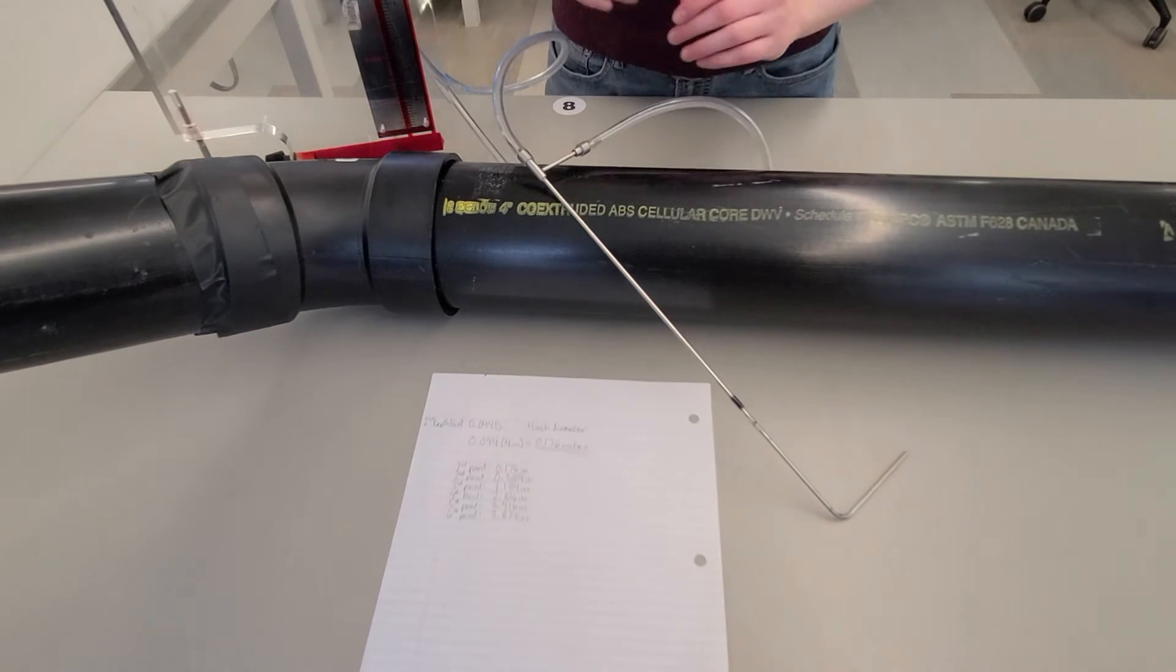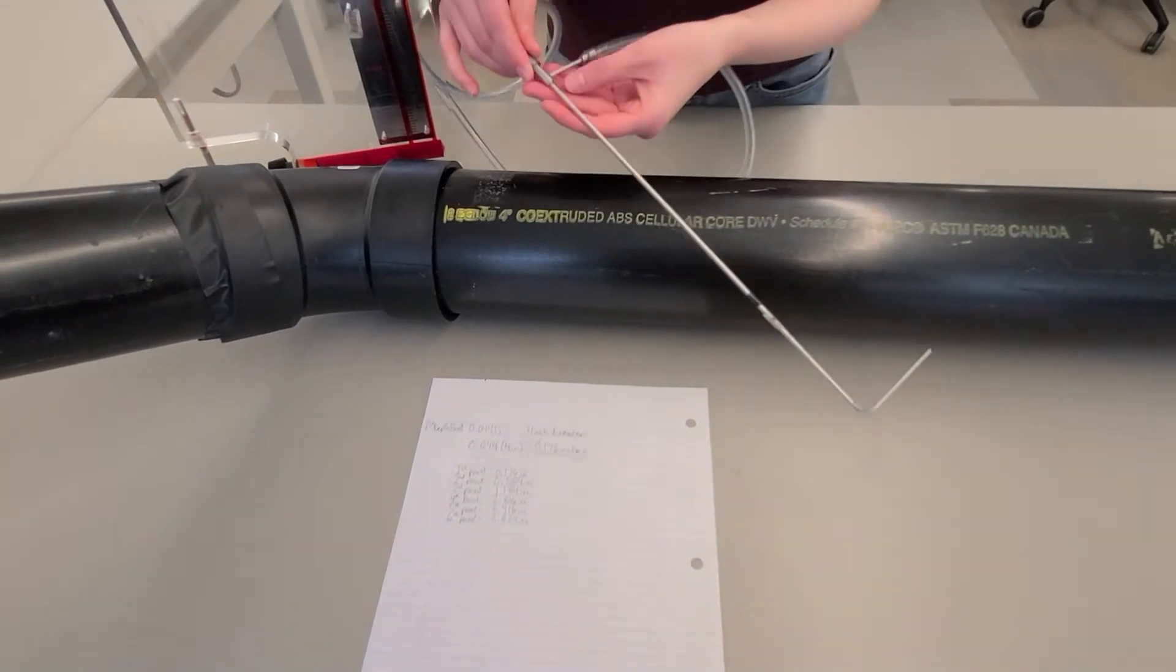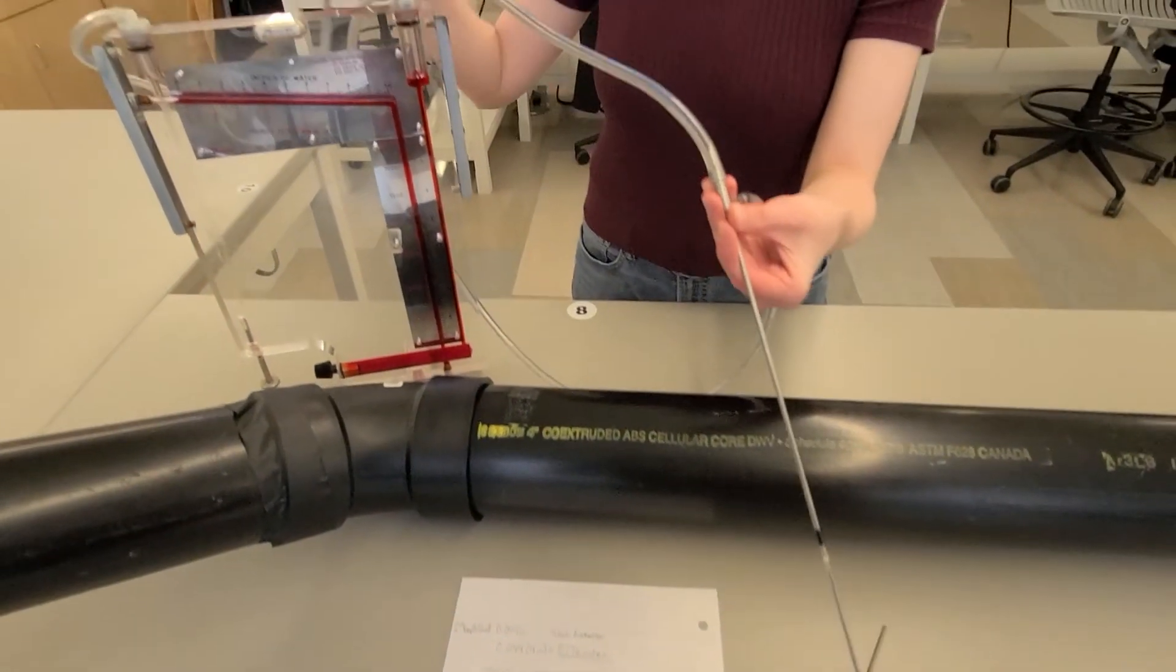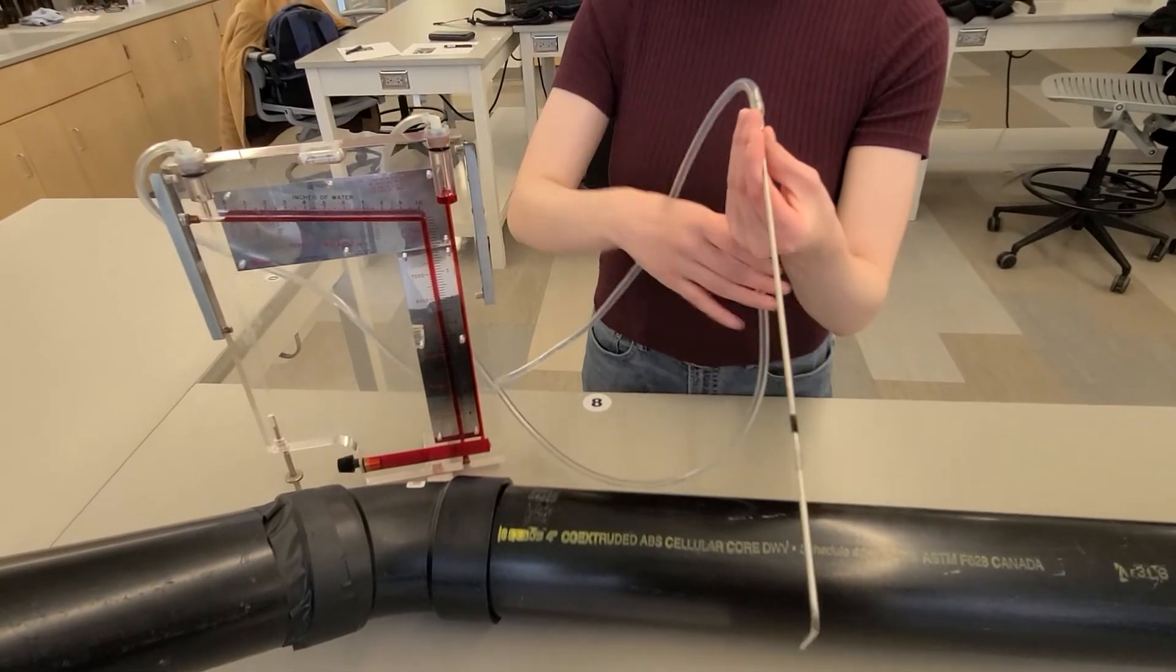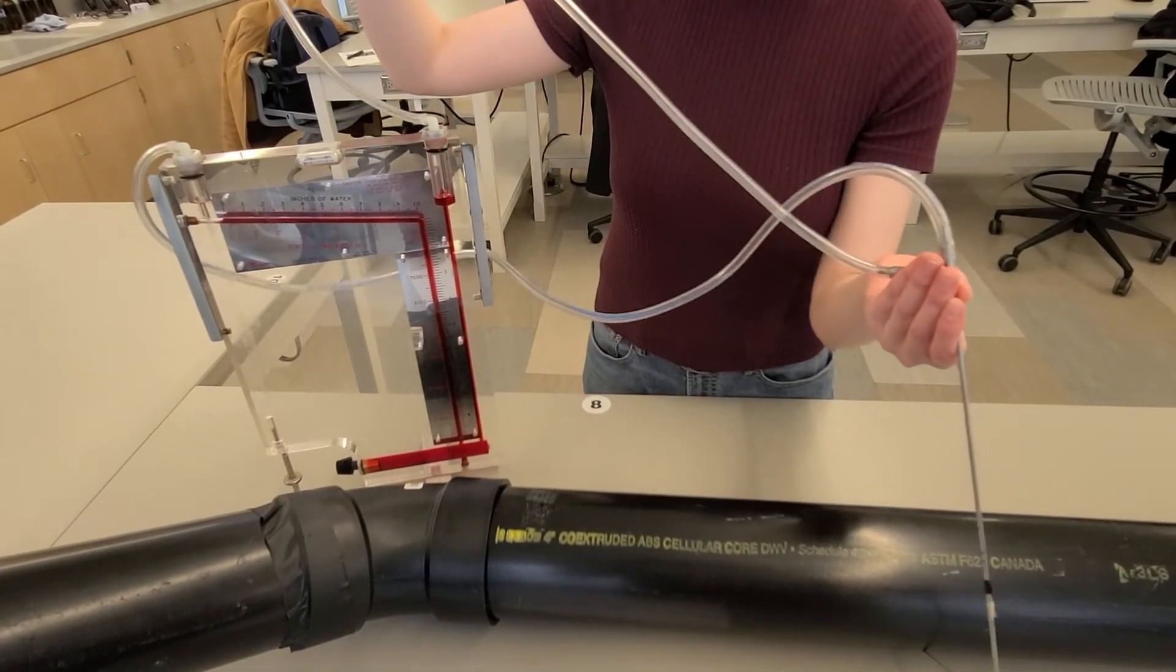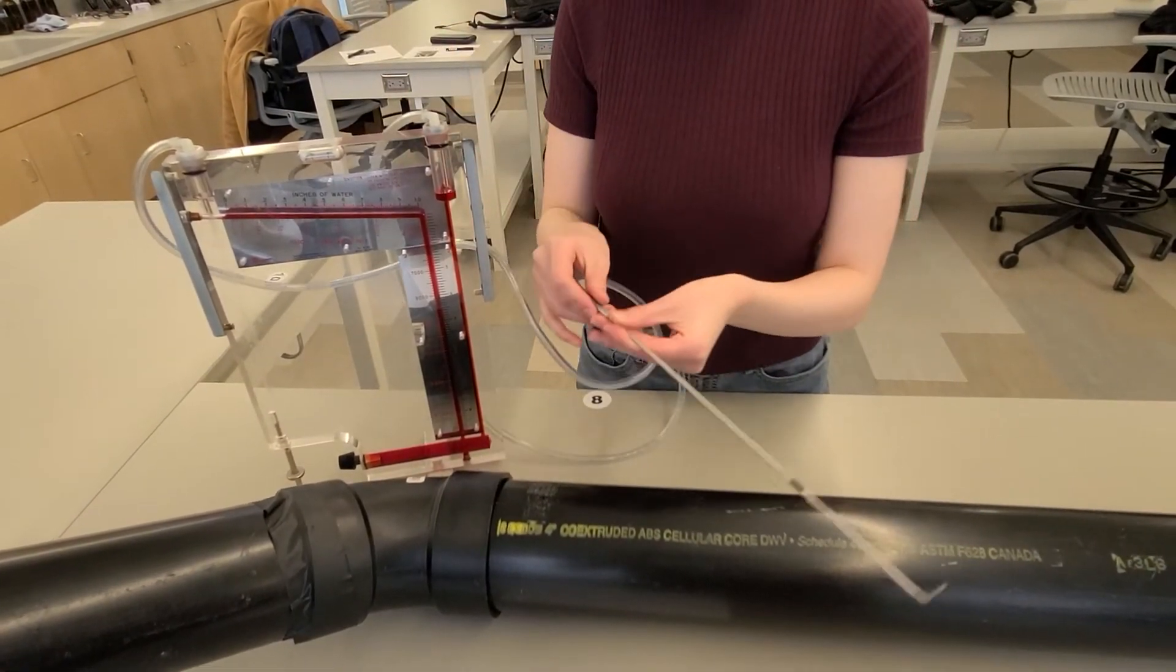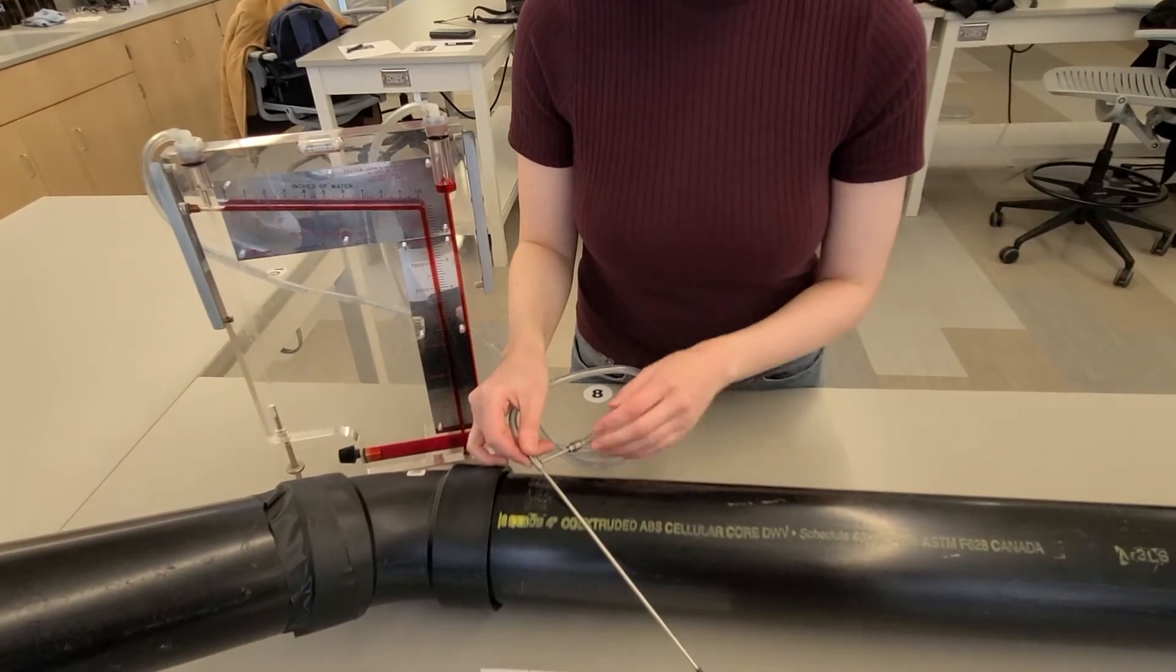Here we've set up a pitot tube to measure the velocity pressure within the duct traverse. Make sure that your instrument is set up properly to measure velocity pressure and/or velocity. We are using an inclined manometer to measure inches of water gauge for velocity pressure.